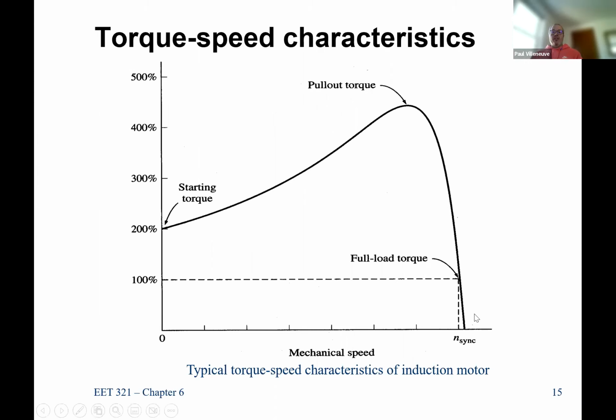It's going to operate a little faster. That's generally okay, because most of the time, like if you're in a pumping application, once you start spinning faster and faster and faster, sometimes that pumping speed will slow down because you're getting less efficient. If it's continuing to do that, your mechanical system has to be designed to handle that additional flow, or you put in a variable frequency drive.